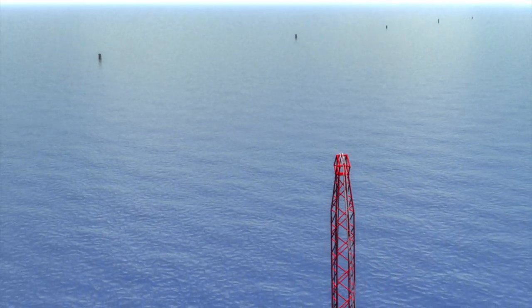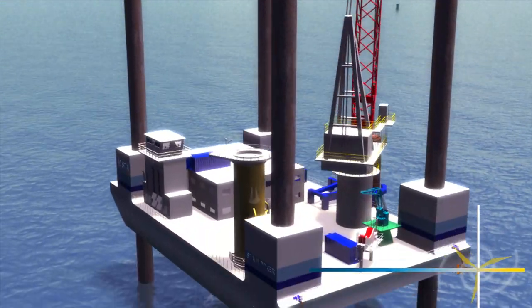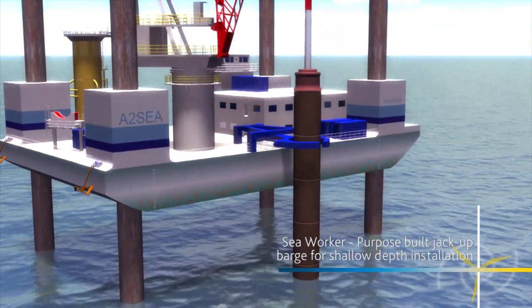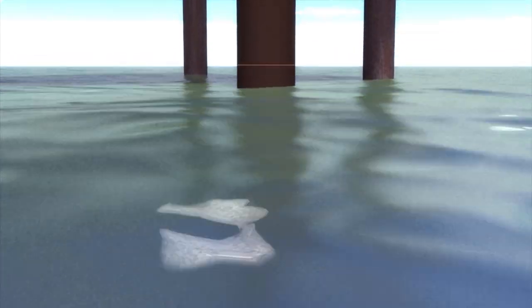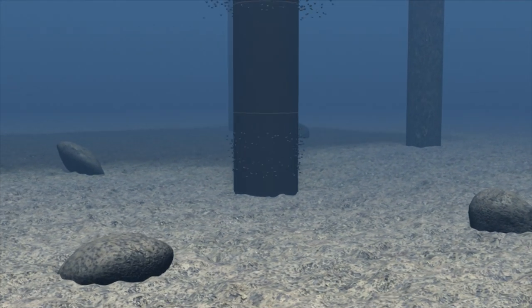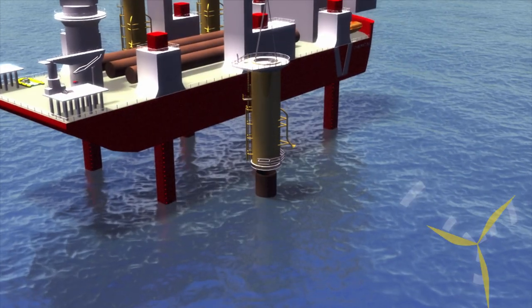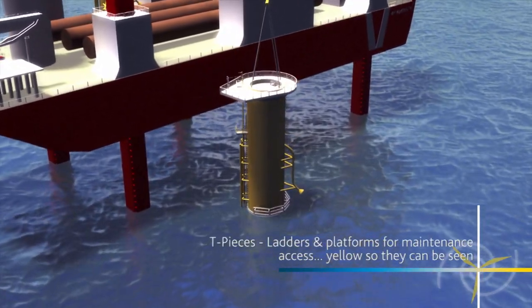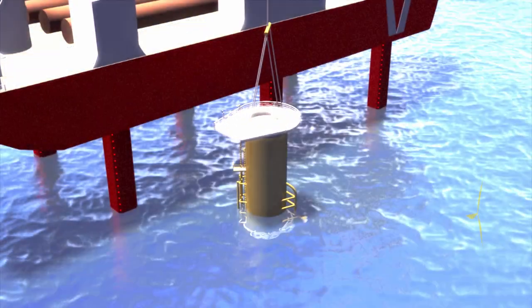Once mobilised, purpose-built vessels, three with long legs lowered onto the seabed to create stable working platforms, will be used for the installation. Firstly, monopiles — long cylindrical steel tubes hammered into the seabed — providing a secure foundation for the turbines. Once ready, onboard cranes are used to mount the yellow transition pieces onto the piles, and grout is filled between the two to secure them in place.